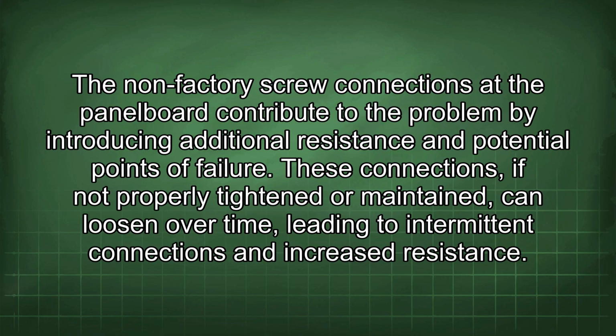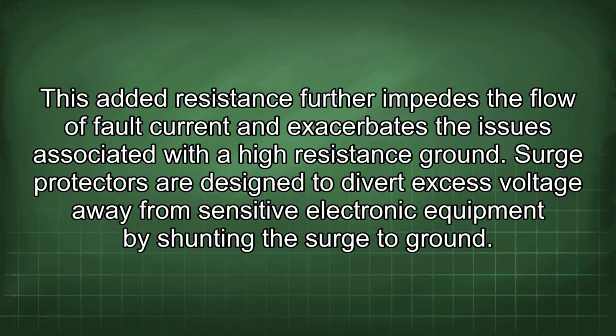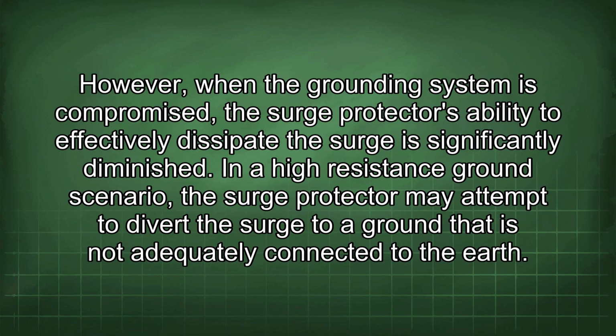electric shock. The non-factory screw connections at the panel board contribute to the problem by introducing additional resistance and potential points of failure. These connections, if not properly tightened or maintained, can loosen over time, leading to intermittent connections and increased resistance. This added resistance further impedes the flow of fault current and exacerbates the issues associated with a high resistance ground. Surge protectors are designed to divert excess voltage away from sensitive electronic equipment by shunting the surge to ground. However, when the grounding system is compromised, the surge protector's ability to effectively dissipate the surge is significantly diminished. In a high-resistance ground scenario, the surge protector may attempt to divert the surge to a ground that is not adequately connected to the earth.